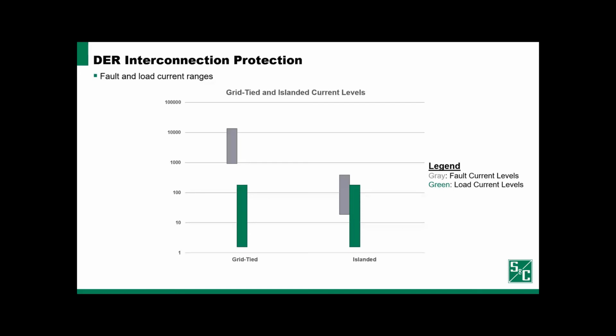This is useful, and this characteristic of systems is something that we leverage in setting our protective device settings. We often are protecting our distribution systems with overcurrent protection, and this looks for currents to be at higher levels. In grid-tied applications, it's very clear that overcurrent is a useful tool to be able to detect these events.